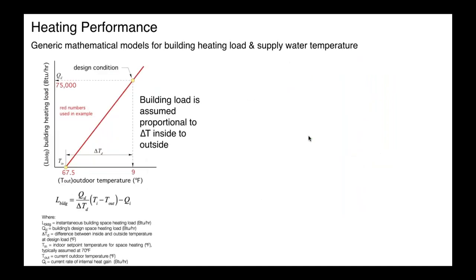Okay. Now, what we're leading up to here is a spreadsheet that's going to model the performance of these systems. So we need to have some way to calculate, at least estimate, what the building load is as the outdoor temperature varies. Well, we're using a very simple linear model right here. It's basically saying that the heating load of the building is proportional to the difference between the inside and the outside temperature. And if you have a known internal rate of heat generation, you could subtract that. So you can think of this as the net effect, the net requirement for heat input from the heating system.